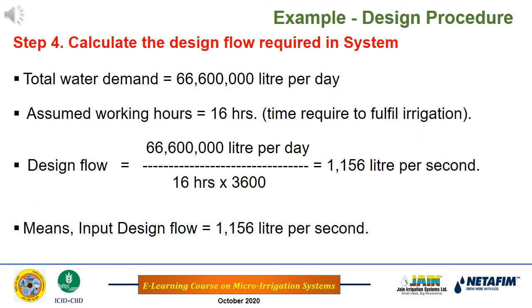Step 4, calculate the design flow required in system. Total water demand is 66,600,000 liter per day. Assume working hours 16 hours, time required to complete the irrigation. Design flow is calculated as water demand divided by working hours. Here water demand is 66,600,000 liter per day and working hour 16 divided by 3,600. Convert this into second. So it comes to 1,156 liter per second, means input design flow equal to 1,156 liter per second.